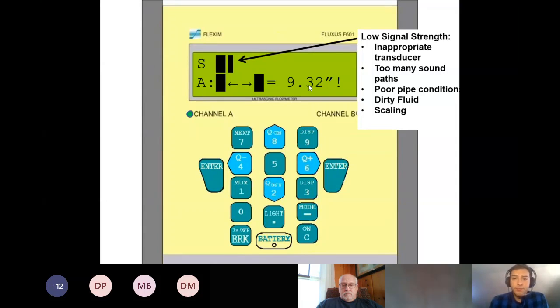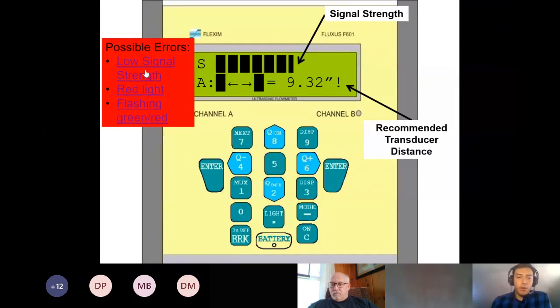Poor pipe conditions or scaling on the pipe or corrosion could also cause signal strength being low. The best thing to do with that would be to try to move it to a different spot in the pipe where the pipe maybe isn't as rusted or scaled. Or just the fluid could be dirty. It could be a poor application. That's for low signal strength.